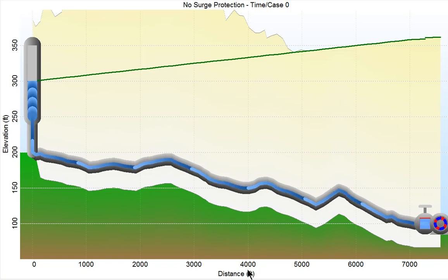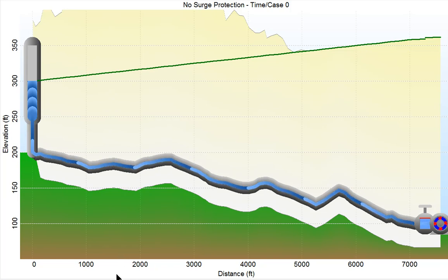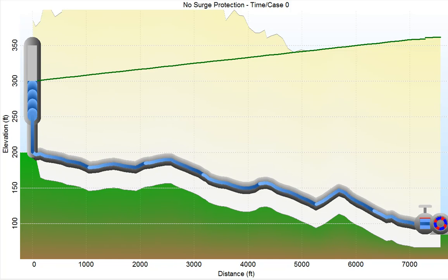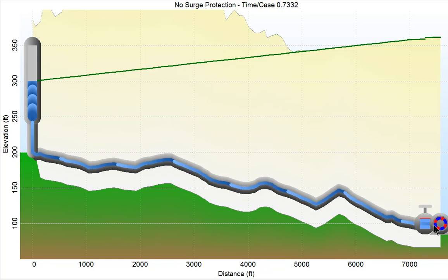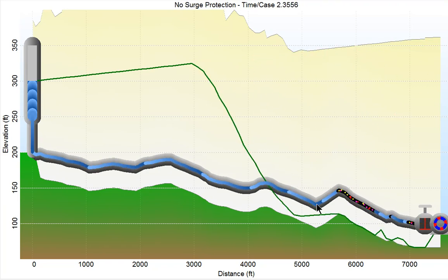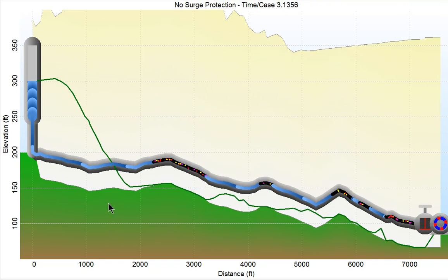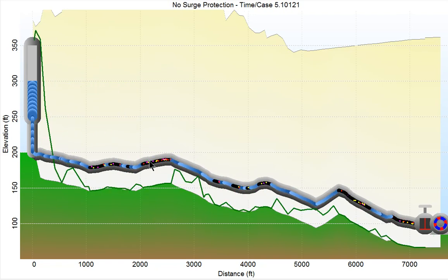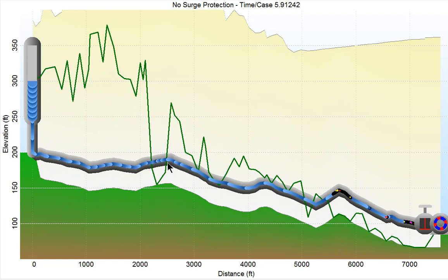We can basically play this and it will show the results of the analysis. Initially the flow is going from the pump to the tank. As we play it, you'll see that the pump slows down, the valve trips very quickly, and as the wave goes down the line, you get negative pressures and cavitation. As the cavities collapse, you get pressure spikes.